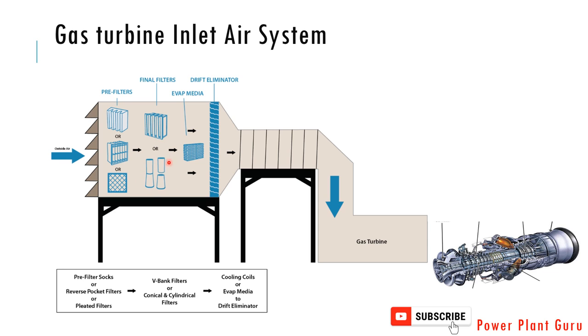These filters may be of different shapes and sizes. One is cylindrical and one is a conical type of filter. These filters are generally three micron in size — they will restrict any particle of more than three microns from going inside the gas turbine.